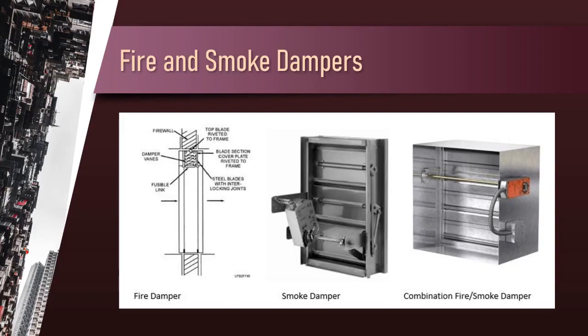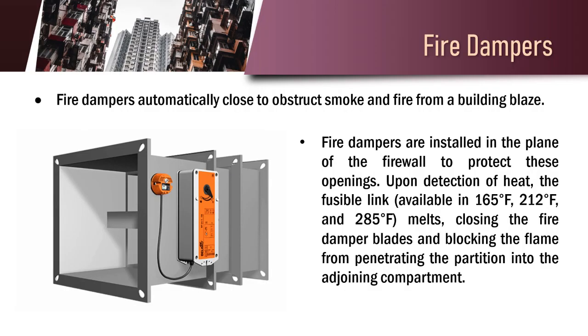Fire and smoke dampers. Fire dampers automatically close to obstruct smoke and fire from a building blaze. Fire dampers are installed in the plane of the firewall to protect these openings. Upon detection of heat, the fusible link, available in 165 degrees Fahrenheit, 212 degrees Fahrenheit, and 285 degrees Fahrenheit, melts, closing the fire damper blades and blocking the flame from penetrating the partition into the adjoining compartment.